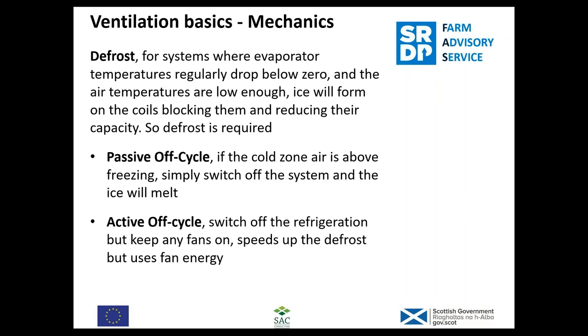One important component to talk about today — which applies to most systems in agriculture, because it's got to do with wet products kept quite low but not all — is defrost. If your evaporator temperature is running regularly below zero, and the air temperatures are low enough — typically when you're anywhere from about three or four degrees below your storage temperature — your refrigerant is likely below zero, at minus two or so. The air cools and will condense water, which is fine, but then it will also freeze. The ice forms on the coil, which is a very good insulator, so it reduces performance, and if it's a blown air system it will also reduce the airflow. So you need to defrost it.